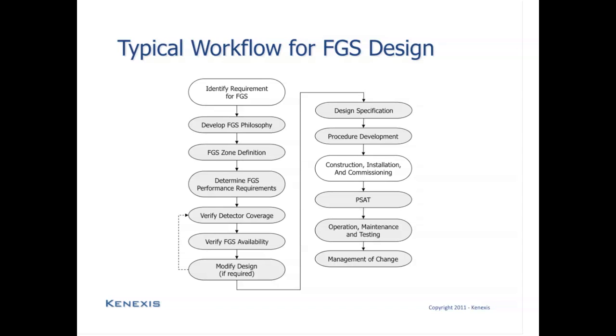And day-to-day operation will include simple things such as responding to alarms, responding to failure alarms, and then periodic function testing and preventive maintenance tasks to ensure that the performance levels that were specified will be achieved through the life cycle of the facility. And finally, we have listed a management of change step. Essentially, any change that occurs to the facility or to the fire and gas system itself needs to be considered, and it needs to drive the design back to the appropriate phase in this typical workflow or the safety life cycle to ensure that as changes are made, the required performance of the system still matches the requirements and the actual design will match.